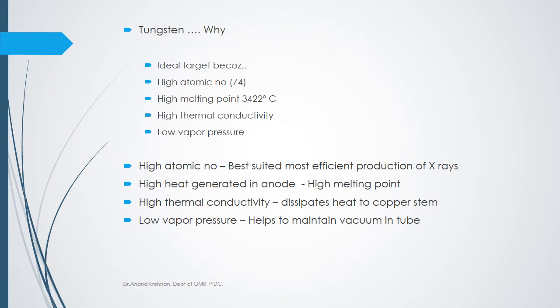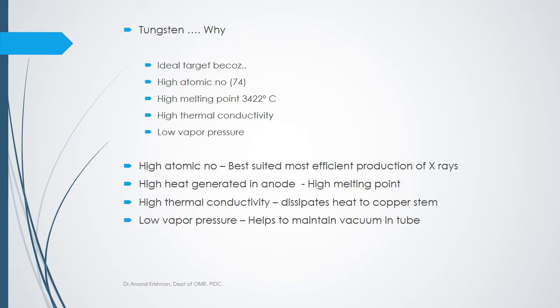Any material subjected to constant heat has a tendency to vaporize. Inside a vacuum tube, vapor would interfere with x-ray production, so we need a material with very low vapor pressure and very high melting point. Tungsten's high atomic number is best suited for efficient x-ray production; its high thermal conductivity dissipates heat to the copper stem, and its low vapor pressure helps maintain the vacuum.